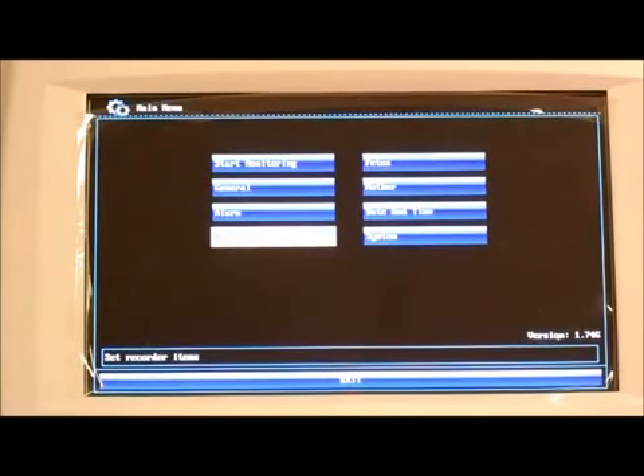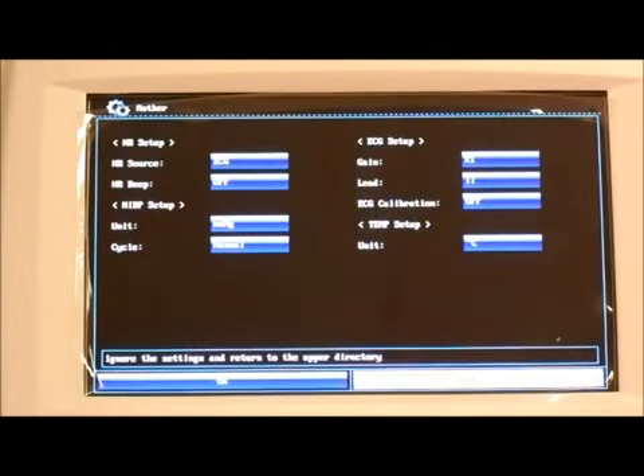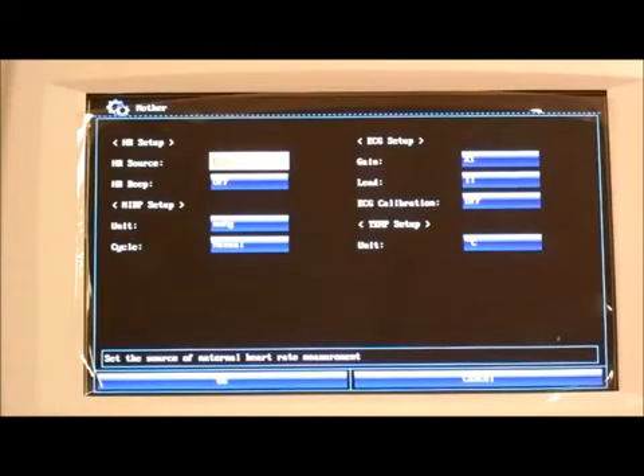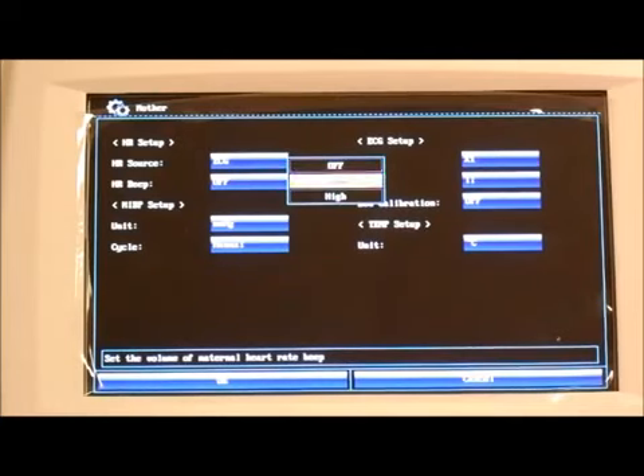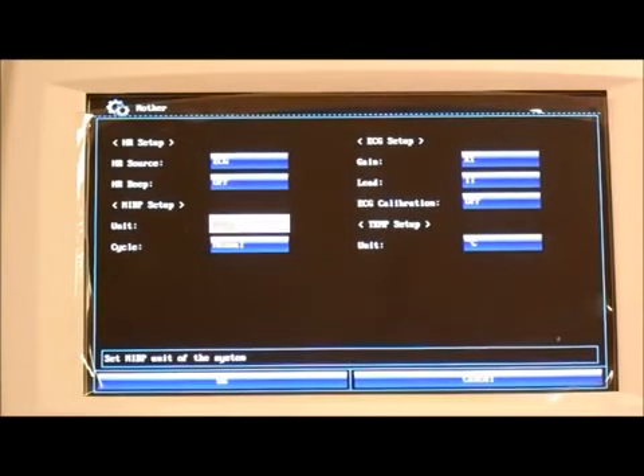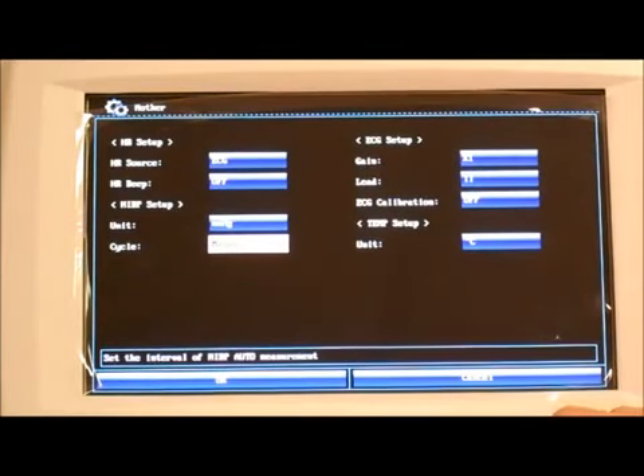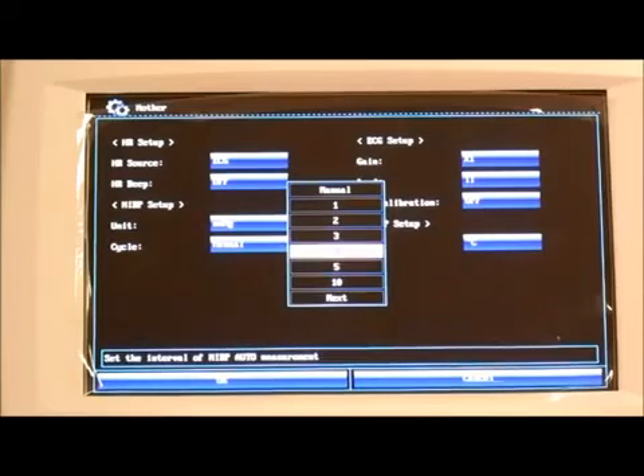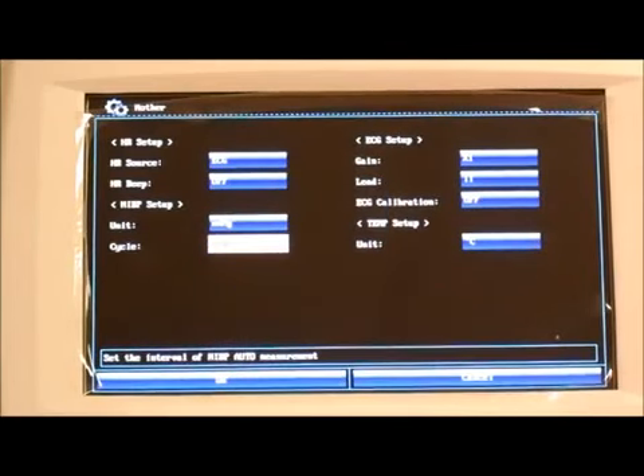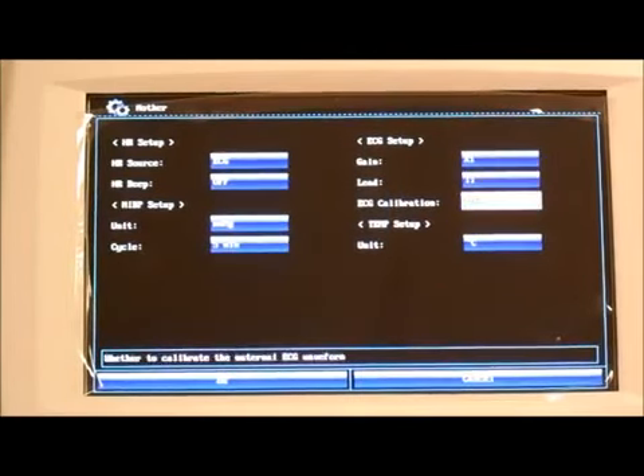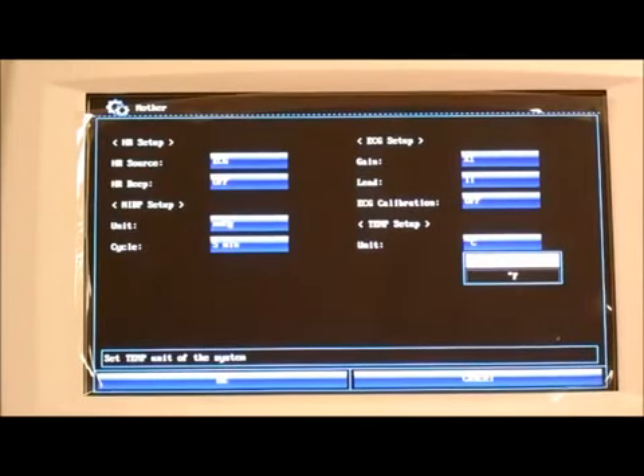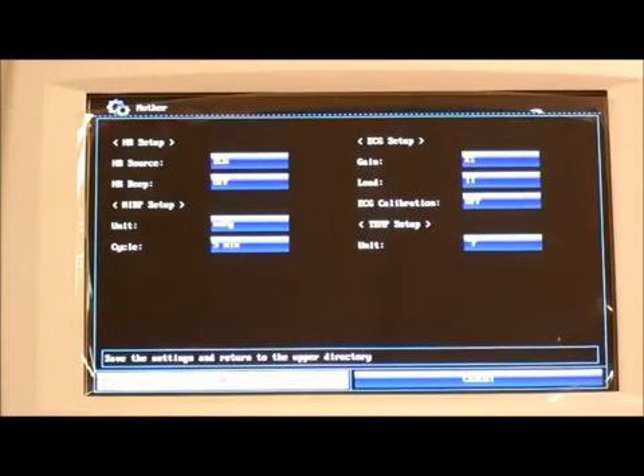Okay, the other setting or menu of interest is the mother. Here is where we can adjust the settings related to the maternal parameter. So your ECG, you can set the heart rate beat to be off, low, or high. Your NIBP, the cycle setting, if it's manual, it'll take a reading only when you press the NIBP key. Or if you set, for example, a setting of 5, it'll take a reading automatically every 5 minutes. And your unit, this is your temperature unit if you're using the temperature transducer, Fahrenheit, here in the US.